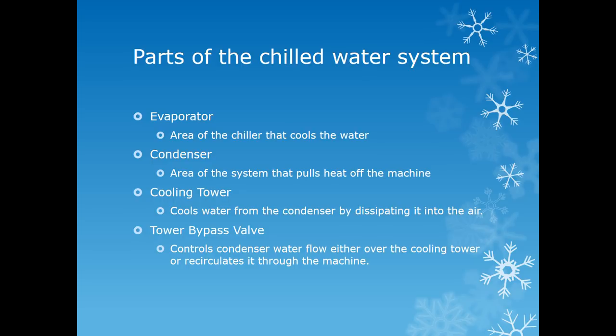The cooling tower is part of the condenser side which actually removes the heat from the condenser water loop. The tower bypass valve is used to regulate the temperature of the condenser water. If the condenser water gets too cold or too hot, the machine can have problems. It must be maintained within a set point of design by the manufacturer of the chiller.